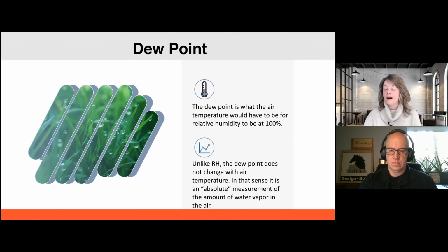Or ductwork starts experiencing condensation. And in building science, in hot, humid climates, the recommendation for ventilation is to try to put a slight positive pressure on the house using some supply ventilation, not balanced, but a little supply. And that is trying to stop the hot air coming in, the wet air coming in, to prevent condensation in our walls. So dew point is very important to understand. And we've got a tool that I'm going to show here in a couple minutes. That's an app that's really helpful in understanding dew point.